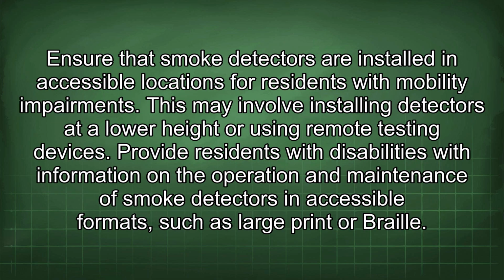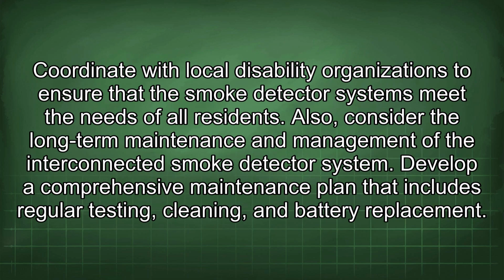Ensure that smoke detectors are installed in accessible locations for residents with mobility impairments. This may involve installing detectors at a lower height or using remote testing devices. Provide residents with disabilities with information on the operation and maintenance of smoke detectors in accessible formats such as large print or braille. Coordinate with local disability organizations to ensure that the smoke detector systems meet the needs of all residents. Also, consider the long-term maintenance and management of the interconnected smoke detector system.